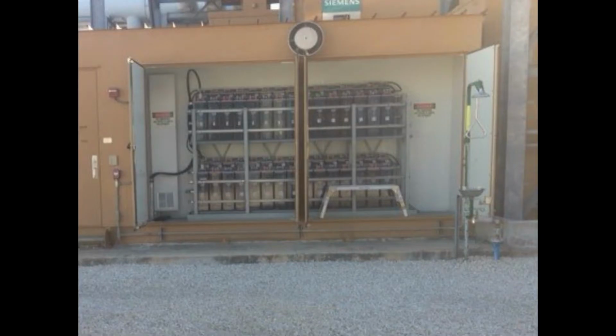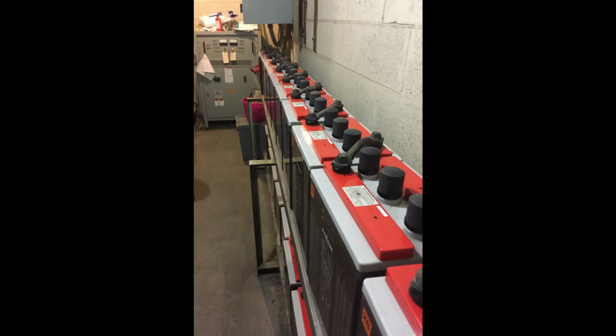Next, you go to that starting point location and measure from the positive post on that cell to ground. What you're looking for is a voltage that is less than 2 volts. If you are above the normal volts per cell, you keep testing cells. You need to continue through the string until you measure less than the 2 volts. Once you've done that, you now have located the cell that is providing the path to ground.